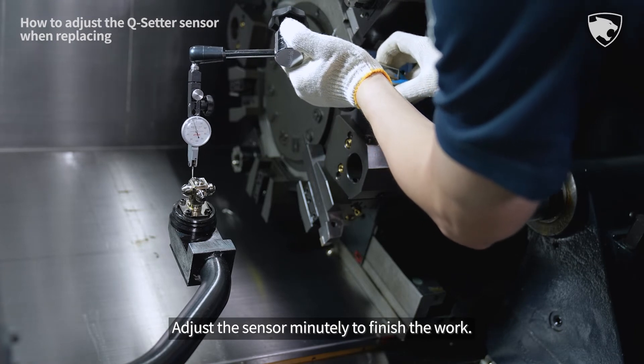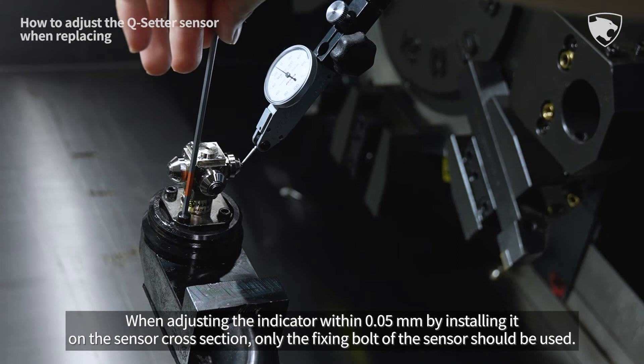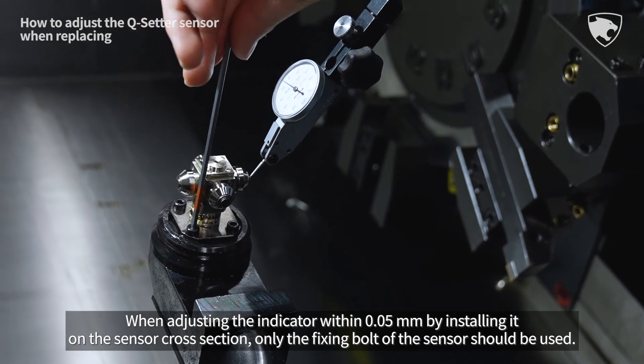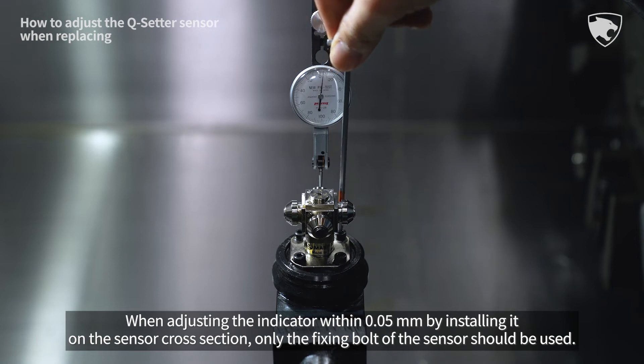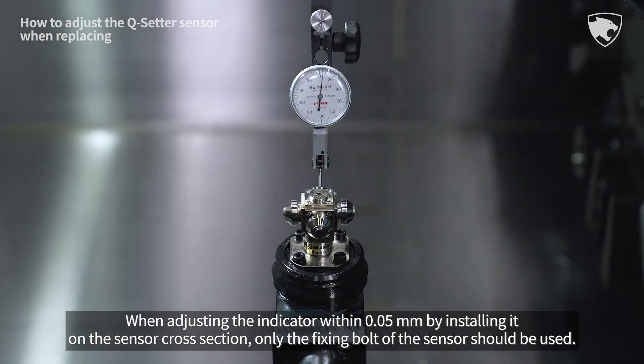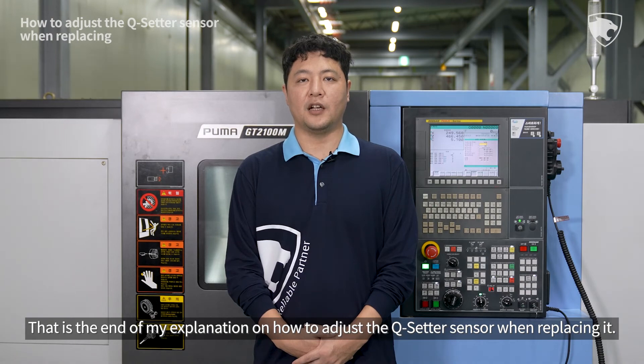Adjust the sensor minutely to finish the work. When adjusting the indicator within 0.05 mm by installing it on the sensor cross-section, only the fixing bolt of the sensor should be used. That is the end of the explanation on how to adjust the Q-Setter sensor when replacing it.